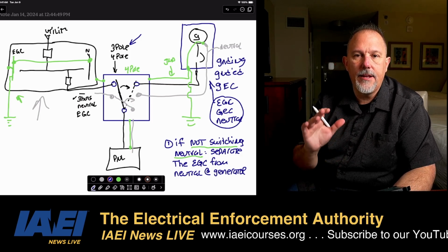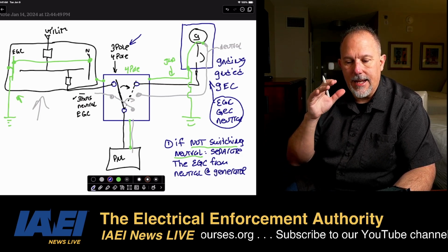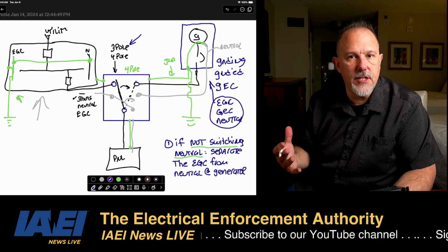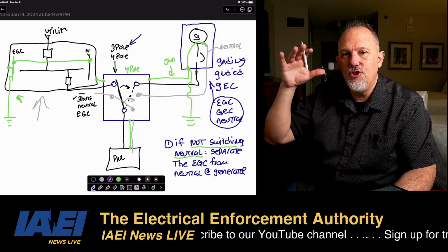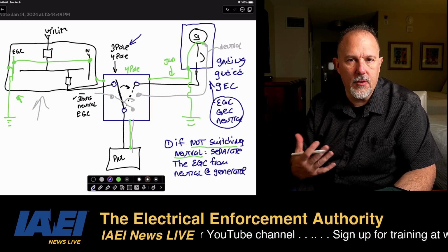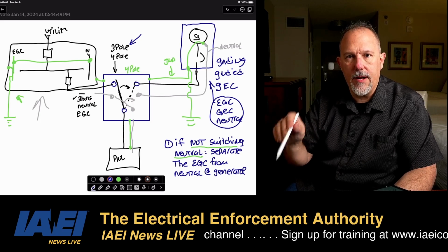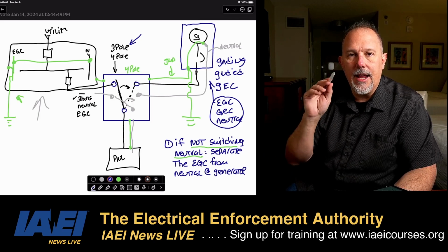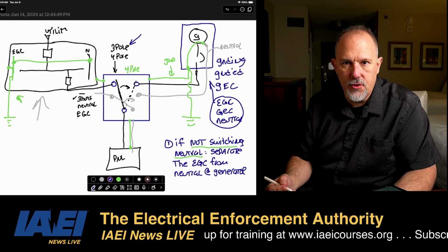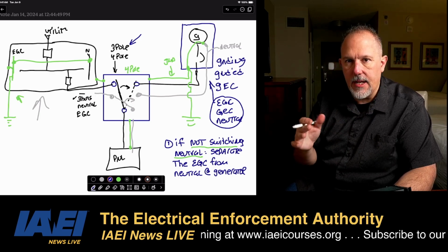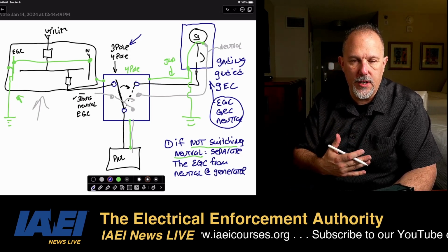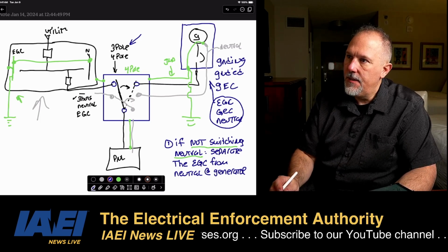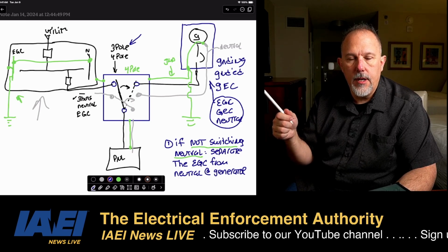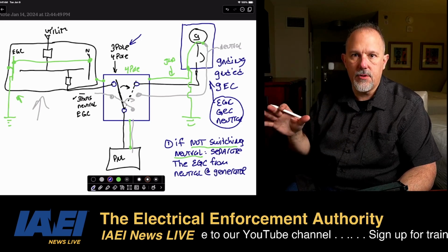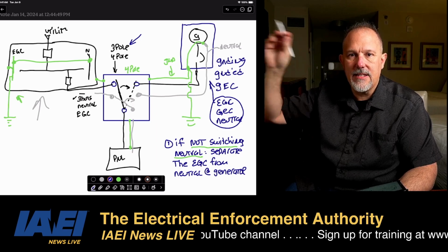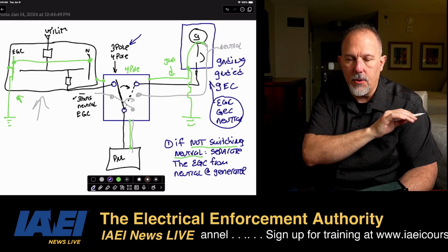I was out at a job site and we were doing an inspection. We opened up the generator and I could see the ground rod that was basically underneath the generator. They must have driven the ground rod, put the generator on top, and then did all of the grounding and bonding. I noticed a connection between the equipment grounding and the grounding electrode conductor connected to that rod and to a terminal strip, and on that terminal strip there was a jumper that bonded with the neutral. Then we went into another building and there was a transfer switch, but it was a 3-pole transfer switch, not a 4-pole. So the inspector said, I'm going to flag this because they're not switching the neutral and they're bonded out there. So now I've got 2 grounds, right? I've got a grounding electrode out there bonded to neutral, and that same neutral conductor is also bonded and grounded in the service panel board. So now I can have circulating currents, etc.